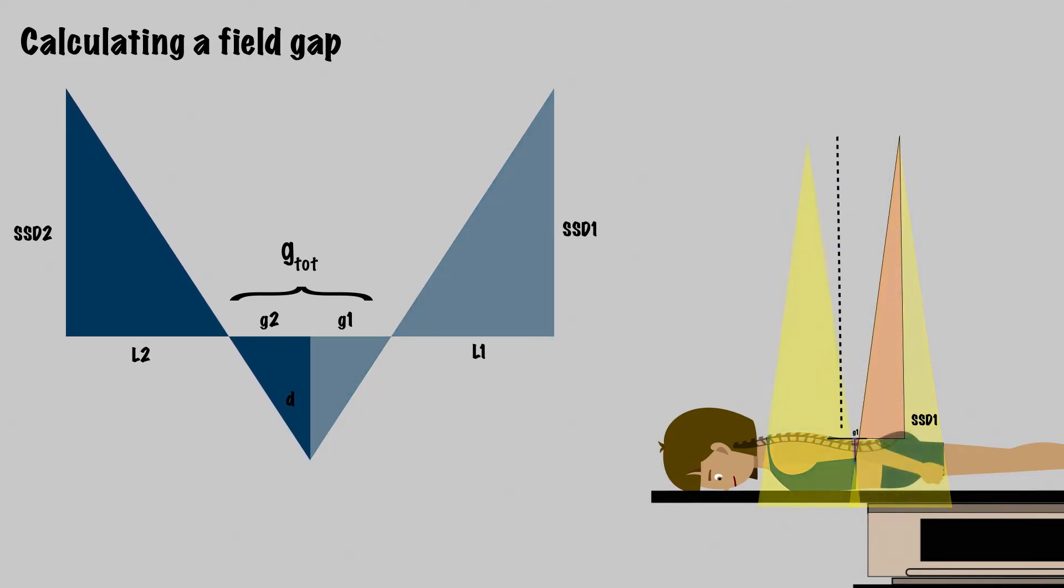To get the full gap, you'll have to repeat this calculation for the other side, which we'll call G2, using L2, which is the length from central axis to the edge of field 2. You could also have different SSDs for the second field, so we'll call this source to surface distance SSD2. Therefore, the total gap is the sum from G1 and G2, so our equation will look like this.